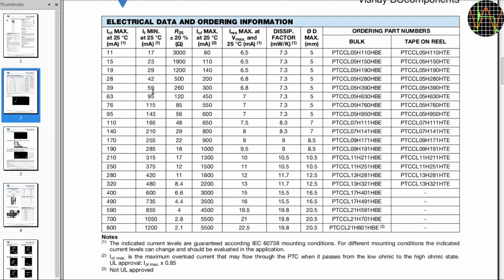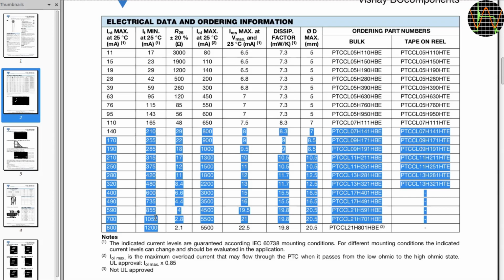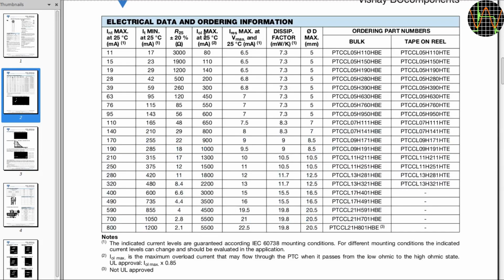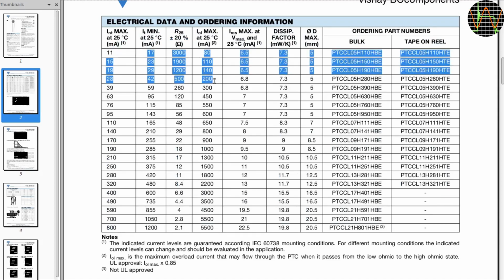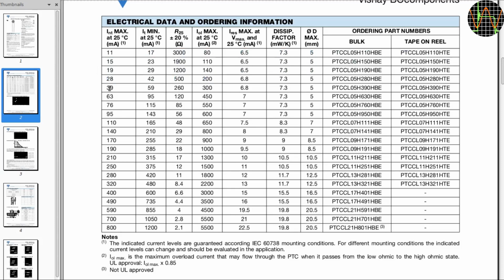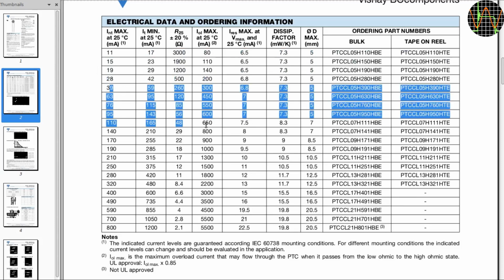In the case of the demagnetizing transformer, the normal power draw is 210 milliamps. That rules out all PTCs with an IT min current greater than that because they would simply not do anything. The second criteria is IOL, which is the maximum overload current. Since the transformer is drawing 210 milliamps, we can't use any PTC that can't handle this current, which rules out the first 4 of this list. We end up with just 5 candidates that would work in our application.